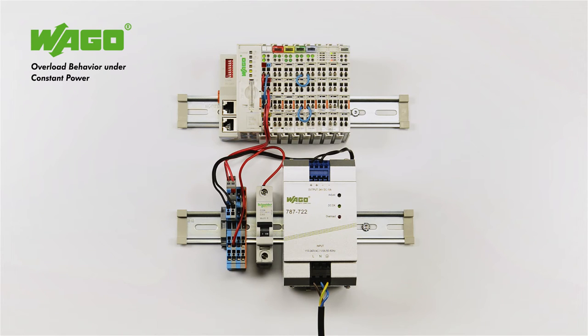Here we want to demonstrate the overload behavior at constant current, respectively power. We are using a 5 ampere power supply unit with constant power behavior and a C2 miniature circuit breaker for the setup. The short circuit is generated directly at the miniature circuit breaker. The power supply increases the output current by lowering the output voltage. This makes it possible to achieve a brief overload of up to 150%. This overload behavior can be used to implement applications with higher startup currents.